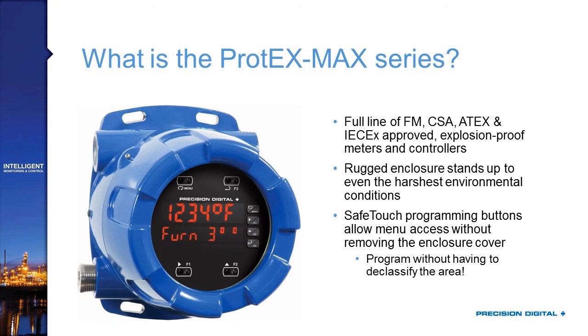The Protex Max features SafeTouch programming buttons — infrared buttons labeled Menu, F3, F1, and F2 — that can be accessed through the glass without removing the cover, so you can operate it in hazardous areas. The core of this product is the ProVu, so it's available in all the same varieties and has many of the same features, including four relays, 4-20mA outputs, and power supplies to run your loops.